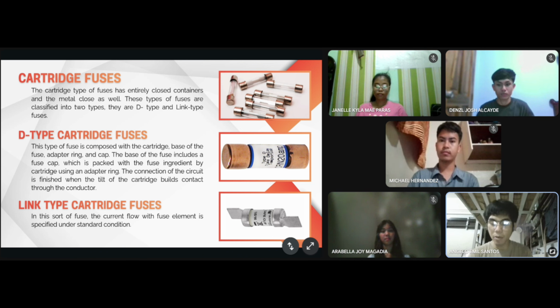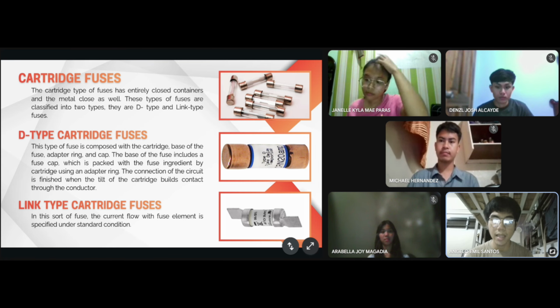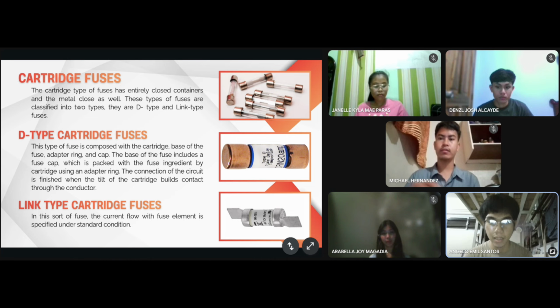Next is for link-type cartridge fuses. Kagaya ng other fuses, it is used to protect the circuit from overcurrent, but it has a replaceable fuse link inside a permanent fuse body. It is also known as HRC or high rupturing capacity or BS type fuse. In a link-type fuse, the current that can safely flow through the fuse link without blowing is specified under standard test conditions. Itong standard test conditions ay maaaring mag-vary, which can be varied into several types including temperature, voltage, and frequency. So for further types and applications of fuses, let's have Mr. Hernandez.